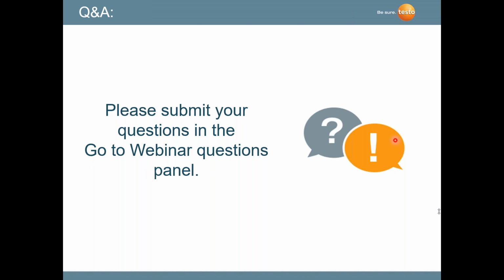Okay, great. Another one is, what are the calibration requirements for your digital gauges? Yes, as I indicated through the presentation, we're using very accurate sensors. We have 2 pressure sensors located internally on the low side and the high side of the instrument. When you turn the instrument on, if you're not reading 0 PSIG, let's say you're reading 0.1 or 0.5, there's a button on the instrument that you press, and it zeroes out the pressure sensors to atmospheric pressure. So that's all you need to do.